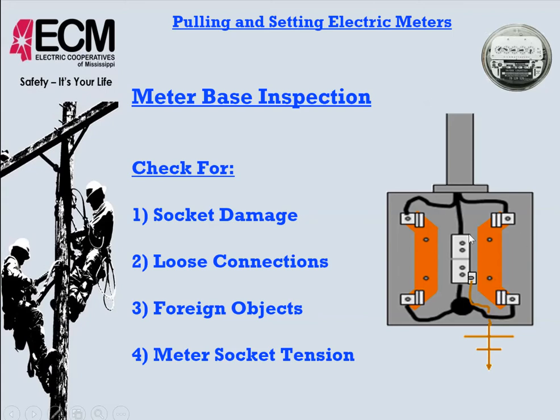Another thing with foreign objects, we don't pull meters as much as we used to, collecting light bills and for disconnects and cutouts for non-payment and stuff. But a lot of times their meter seals and their tabs, if they use the tabs on the lugs, sometimes those get left there. They should not be. And then meter socket tension. This is where the meter actually plugs into, and it's not our meter base.